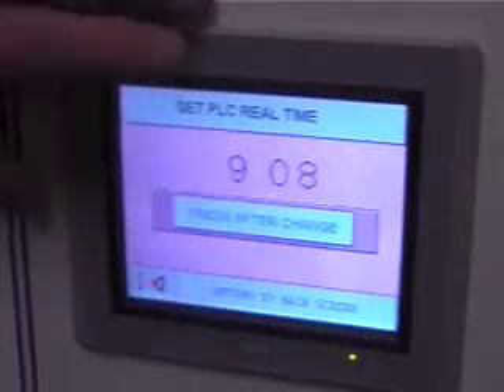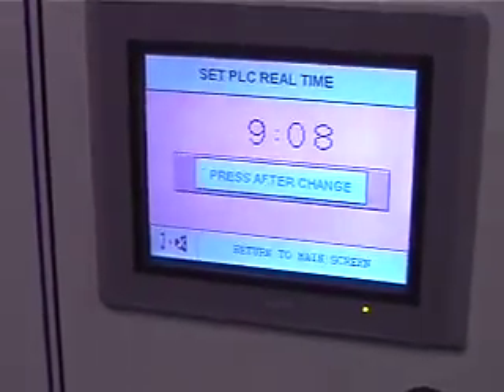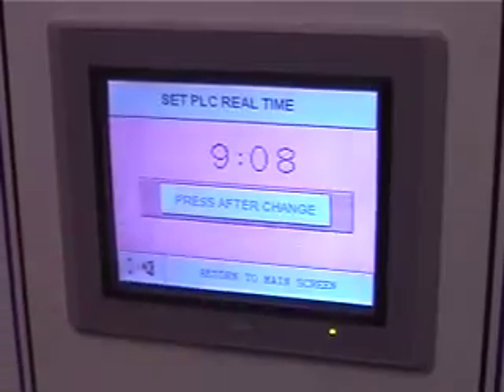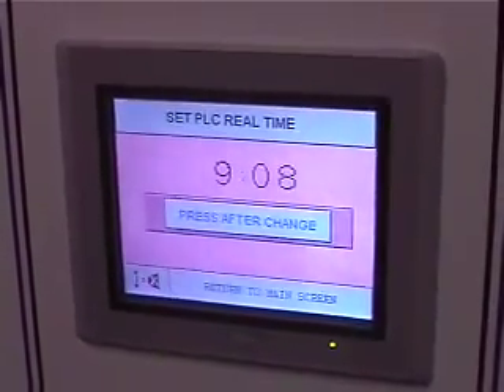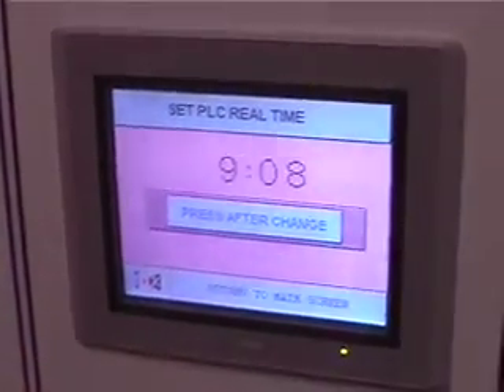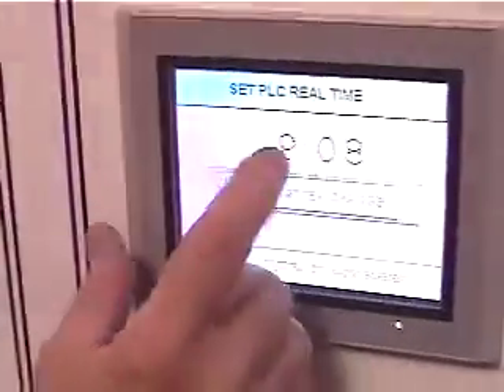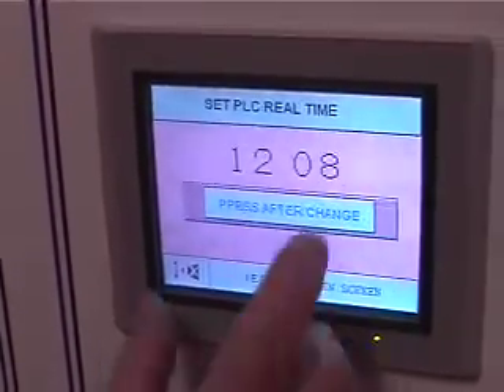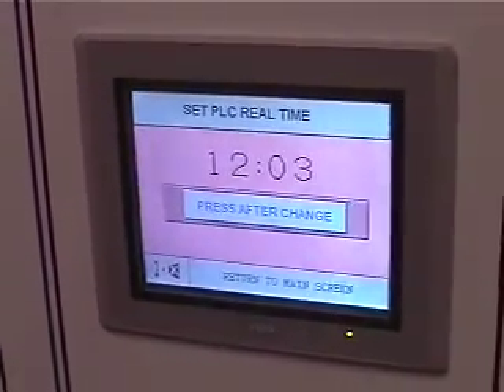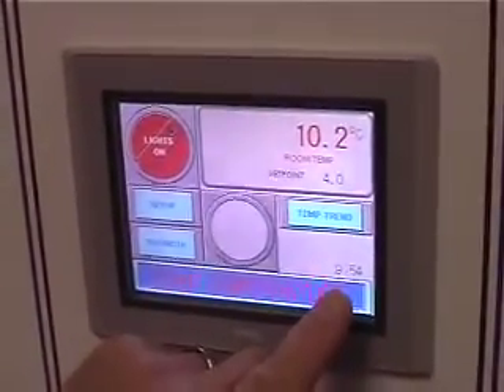We were talking about setting the time. So this time is the time the PLC has. Really the most important thing that this does is the defrost. So it knows, at 12 o'clock it goes in defrost. If you want to change that for daylight savings, do they do daylight savings in Utah? It's not really that important in the overall operation of the room, but if you wanted to keep it clean, you would set up the hour and minute. Say it's 12 o'clock. Let's say it's 03. Okay? We'll go back and you see nothing's changed here.